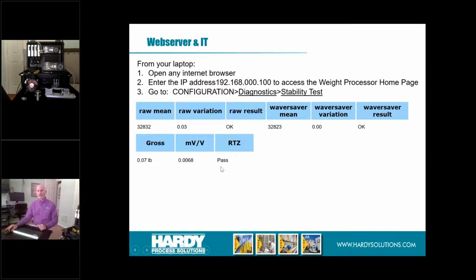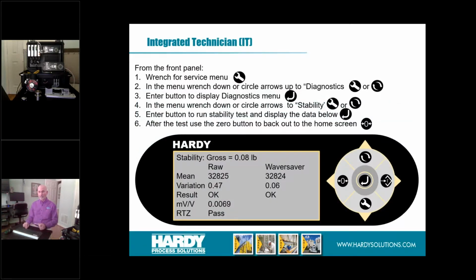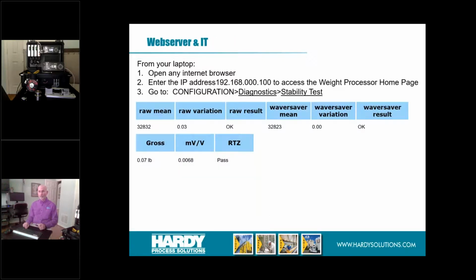The last thing is a return to zero. There is a tolerance set on this, but a return to zero can help you if the tank happens to be binding on something, and when you let the weight off, you don't get the right reading on that return to zero. So that's how you would use the IT, either off the front plate of the display or through the diagnostic view.